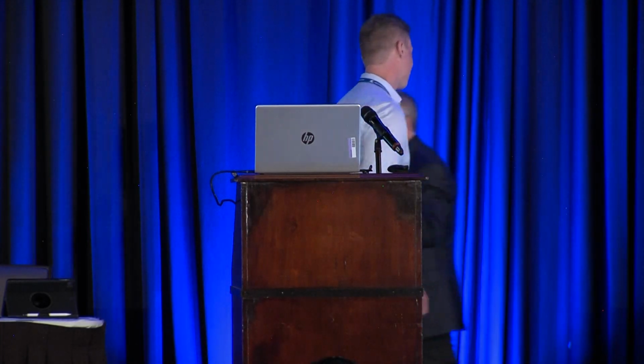Anything else? Okay. At what level will moisture become a problem as an interference? Yeah, so I'm calibrated up to 200 ppm right now. That's kind of our dynamic range with the pressure set point that we're operating at. Usually I will not recommend going above that, not due to interference so much as it's very hard to calibrate a gaseous phase mixture running at pressure. So that's generally our range right now, up to 200 ppm, nothing beyond. Very good. Thank you very much, Trevor. Appreciate the presentation.